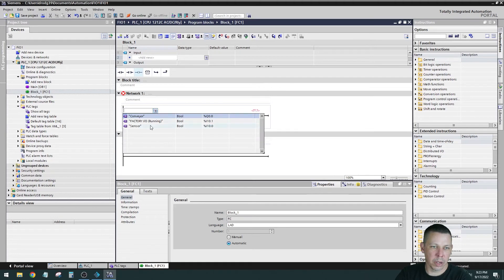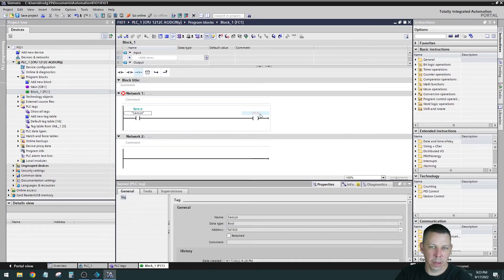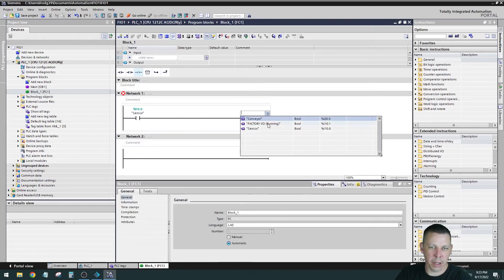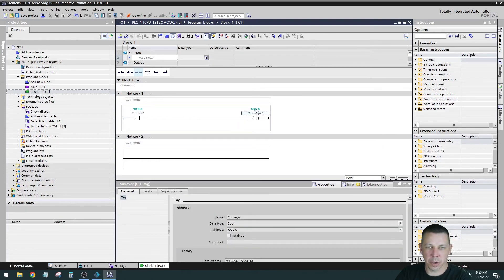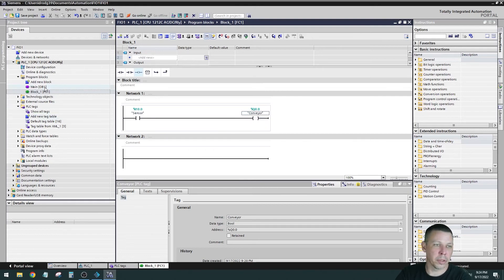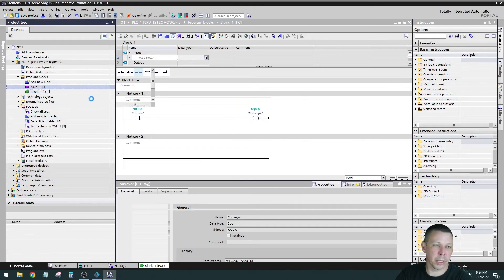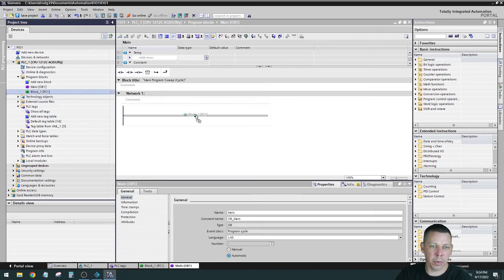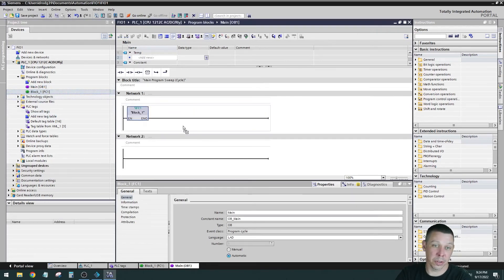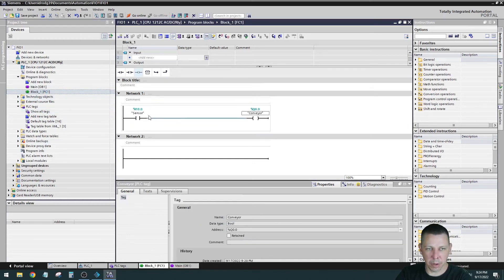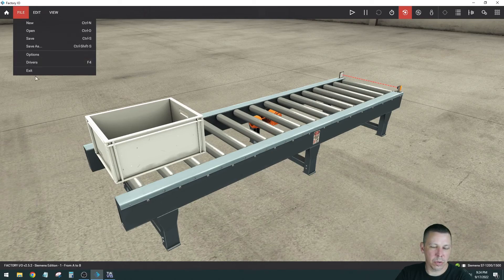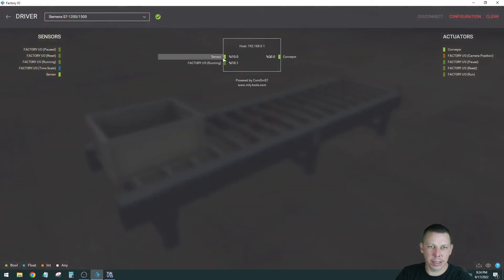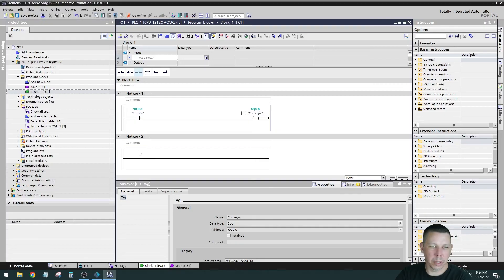Now we have a block here to put our logic in. We're going to make that sensor a normally open contact and we're going to put an output for the motor and that should be all we need. And since we copied our tags over, we can go here and that's the sensor because our tags are already in there and our conveyor is the output. So copied over output Q0.0 and sensor is input I0.0. So that is all the logic we need. But if you remember, we still have to put the function block in OB1 and drag that over to there. Otherwise it won't get executed because the only thing that runs is OB1 when you start the program.